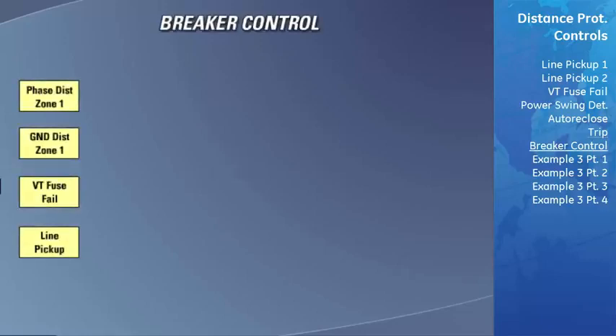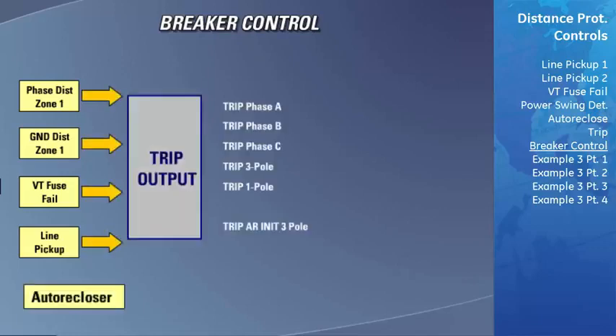Since you have already completed all of the previous sections of this training course, you are now familiar with the process of setting up all of the protection elements that are necessary to protect a transmission line. We have also shown you how to configure all of the various control functions, such as the auto recloser function that is used to automatically close a breaker after transient faults, and the trip output feature that is used to handle all of the tripping logic in the D60.